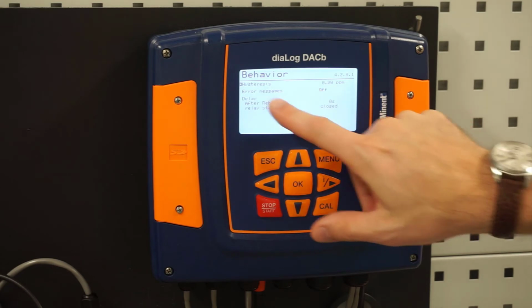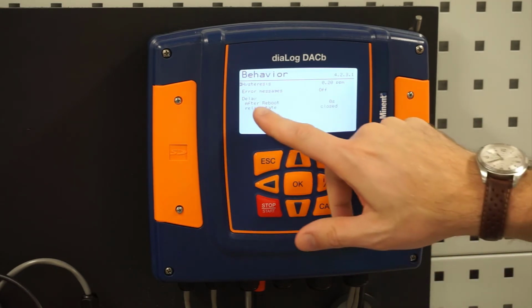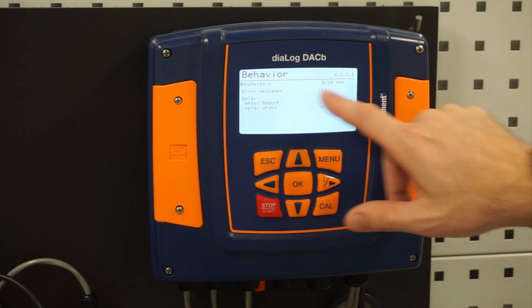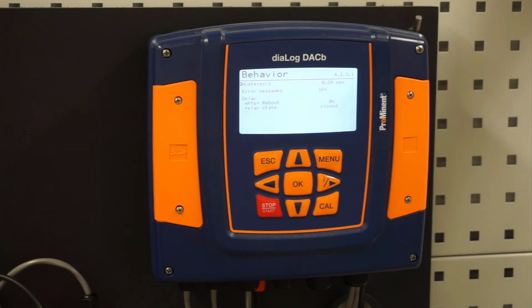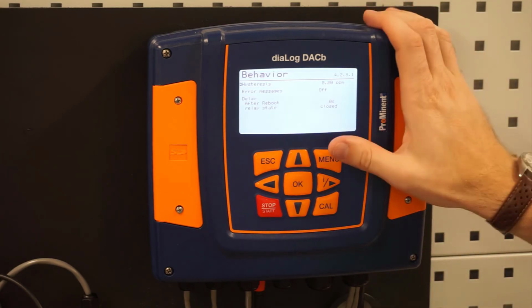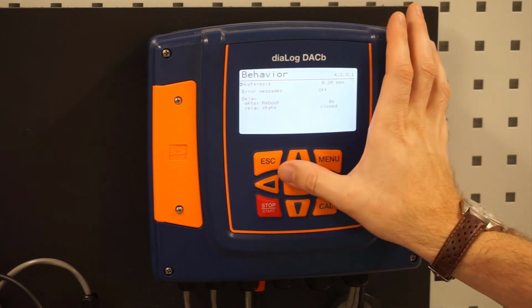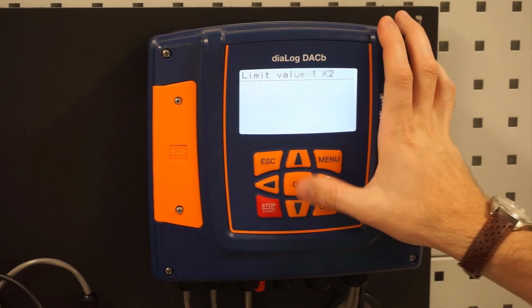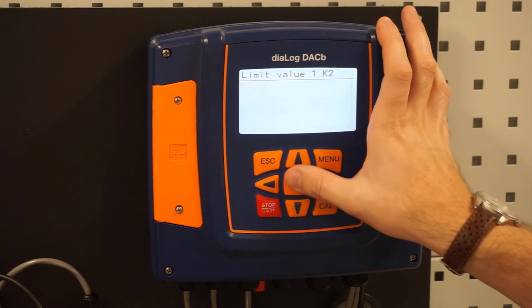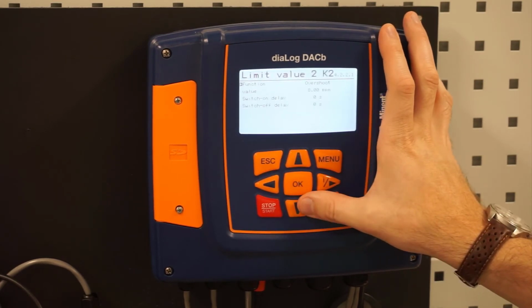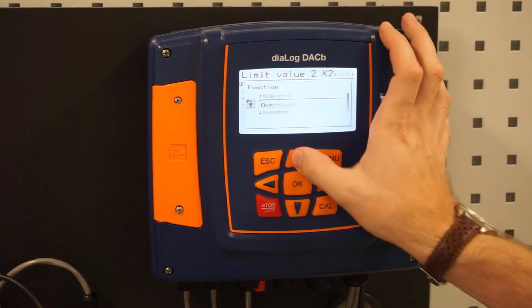Are we going to get an error message if we do that? Right now it's off. And is there going to be a delay on the limit once we reboot? Once we reboot, the controller will look at that limit, and if the value is past it, it's going to trigger that limit. We could increase that delay in seconds after we reboot the controller to delay the initiation of that limit relay. I'm just going to turn these off. We're not using them in this case, so there's no need to have them on the screen, and I can clean up the screen.